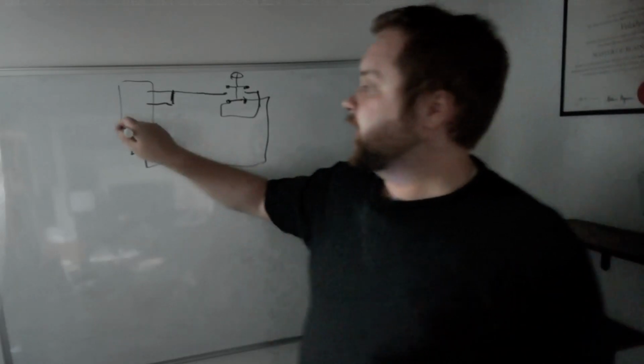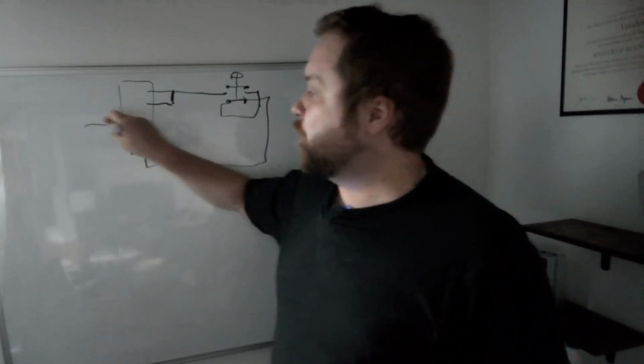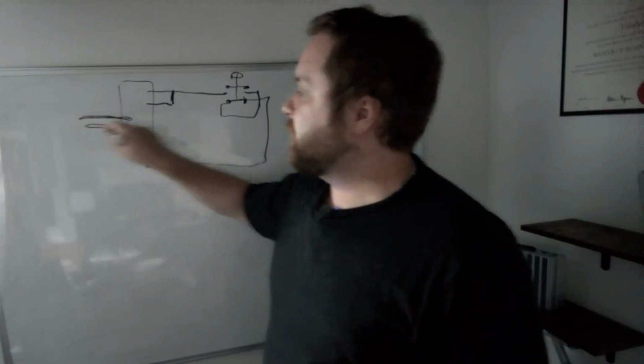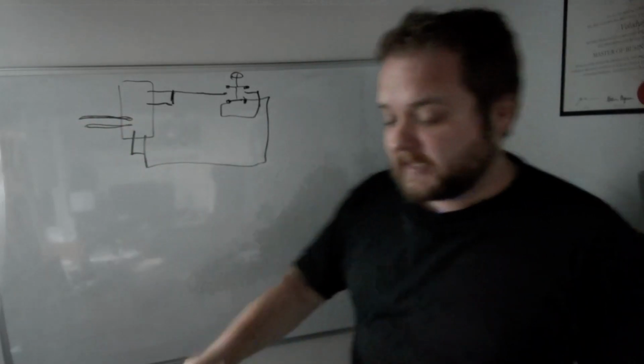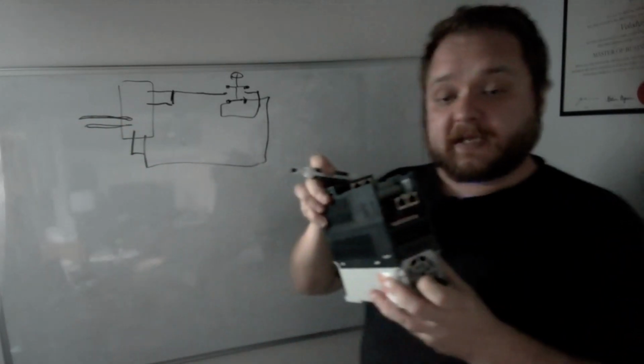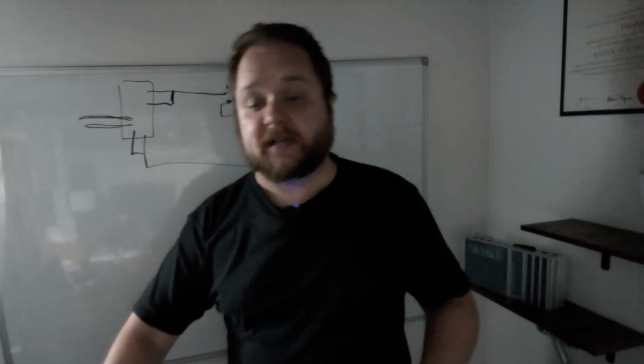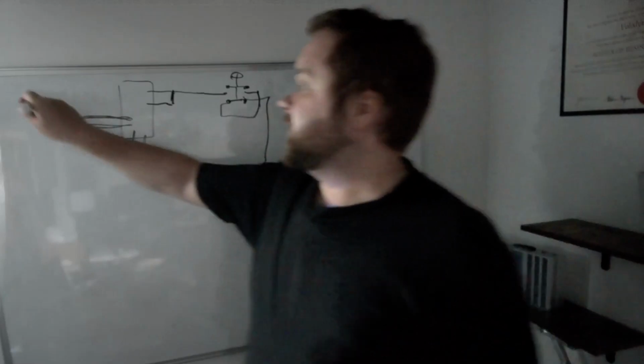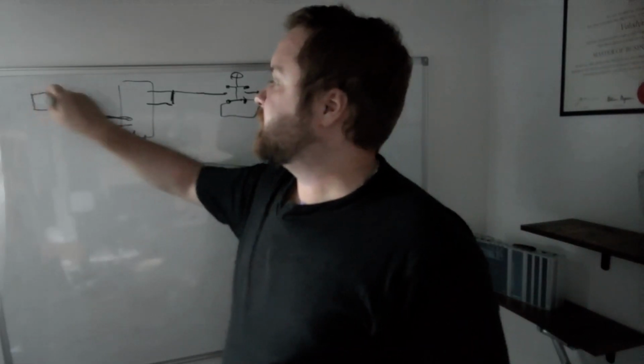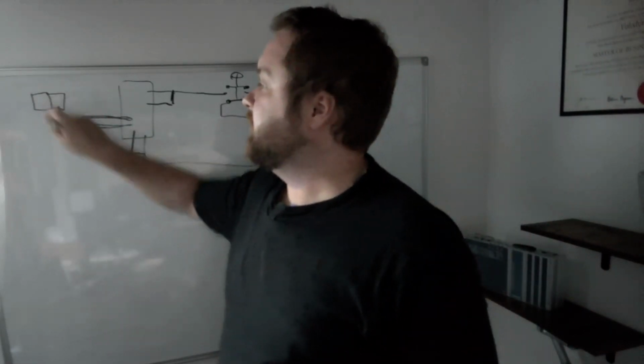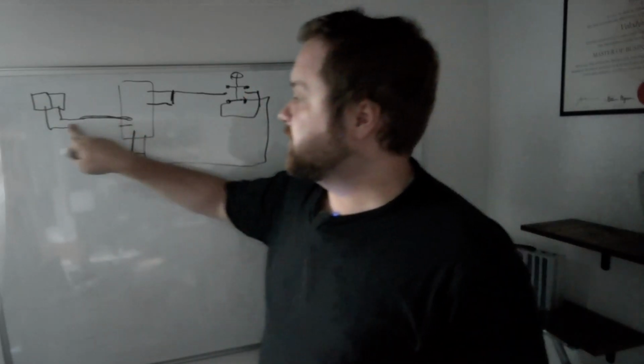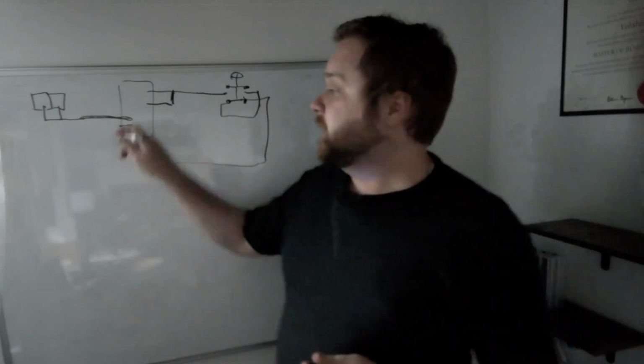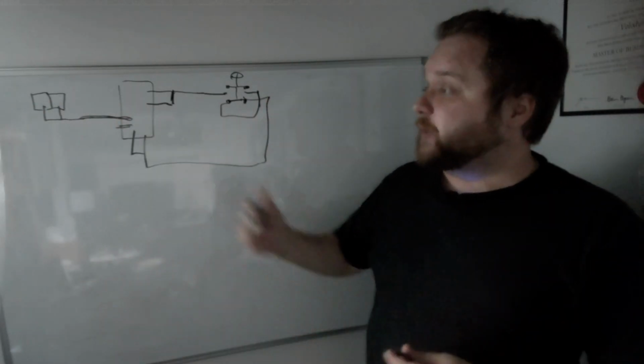The other thing on the output side is, as I mentioned, you always have two signals confirming that something is safe. And as I've mentioned to you on the PowerFlex side, you have two inputs that need to be energized by a safety device in order to confirm its safety. So if you have two terminals expecting dual channel safety, this is the way you should be wiring this. You should never be shorting the two signals to a single channel, because ultimately you are rendering your application unsafe.